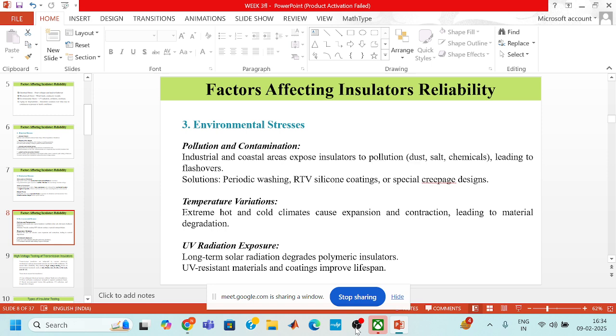For this purpose, we have to provide periodic washing, cleaning, RTV silicone coatings, or some special creepage designs. Second is temperature variations. In extreme hot and cold climates, expansion or contraction can occur, which leads to material degradation. And third is UV radiation exposure. Long-term solar radiation degrades polymeric insulators. In that case, we have to use UV resistant materials and coatings, which improve the lifespan of insulators.